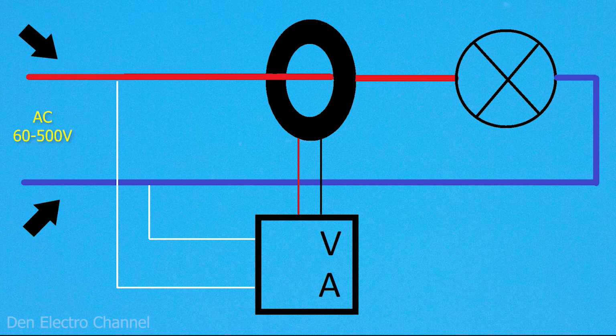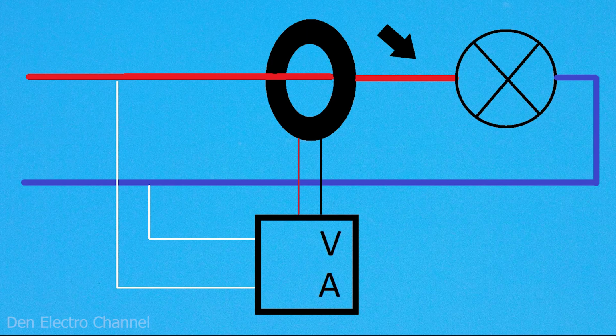These wires carry alternating current, phase and neutral. I've drawn them in red and blue, but in reality it doesn't matter which wire is phase and which is neutral. One of the wires going to the load is fed through the current transformer. I've drawn a light bulb as the load here, but in reality the load could be anything, even a kettle, an iron, or a hairdryer. You could even power the entire house through the current transformer. The second wire is connected directly to the load.